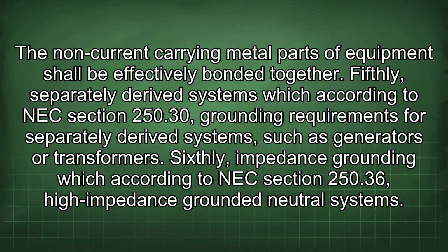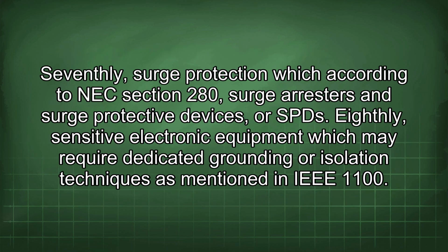Fifthly, separately derived systems, which according to NEC section 250.30, grounding requirements for separately derived systems such as generators or transformers. Sixthly, impedance grounding, which according to NEC section 250.36, high impedance grounded neutral systems. Seventhly, surge protection, which according to NEC section 280, surge arresters and surge protective devices, or SPDs. Eighthly, sensitive electronic equipment, which may require dedicated grounding or isolation techniques as mentioned in IEEE 1100.